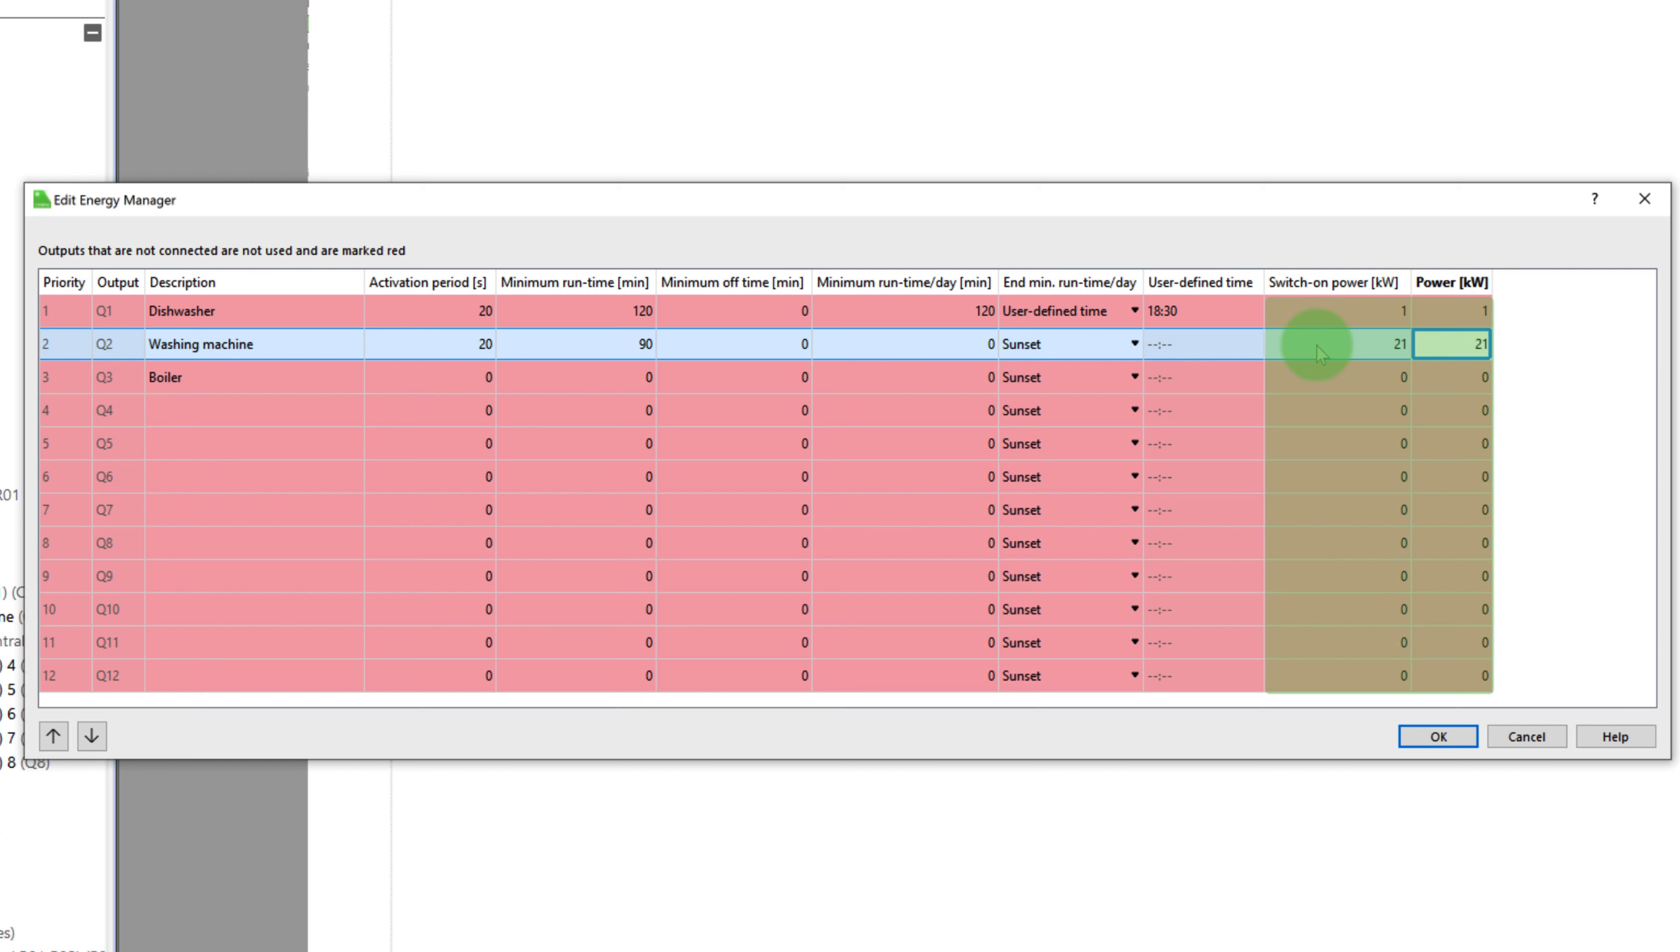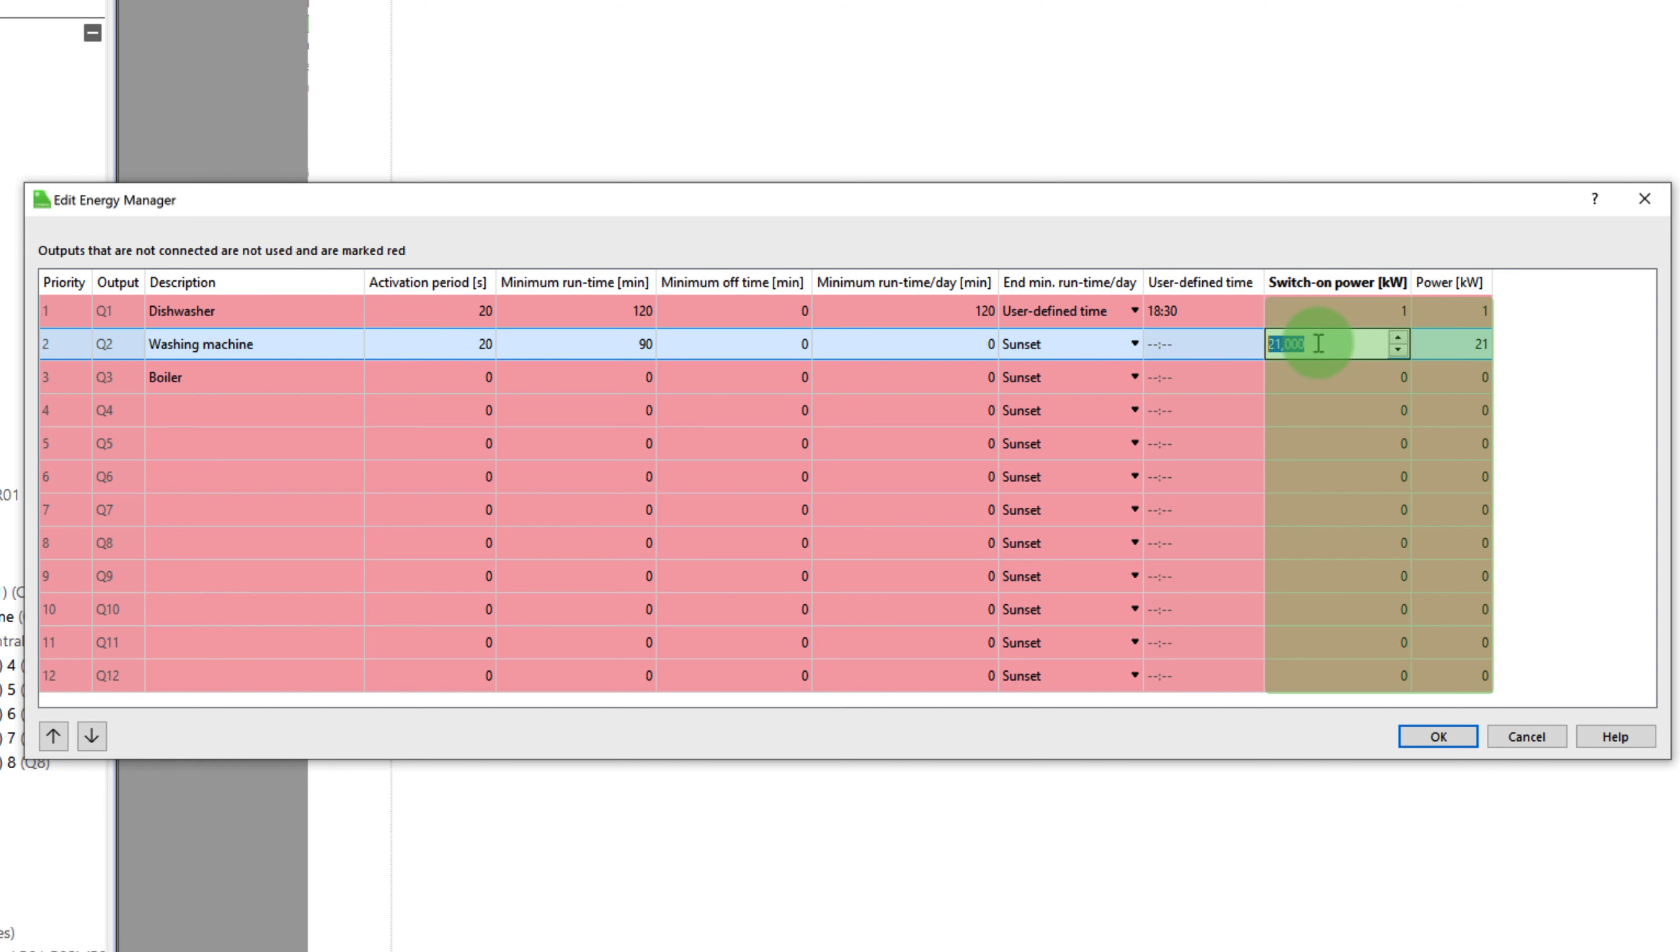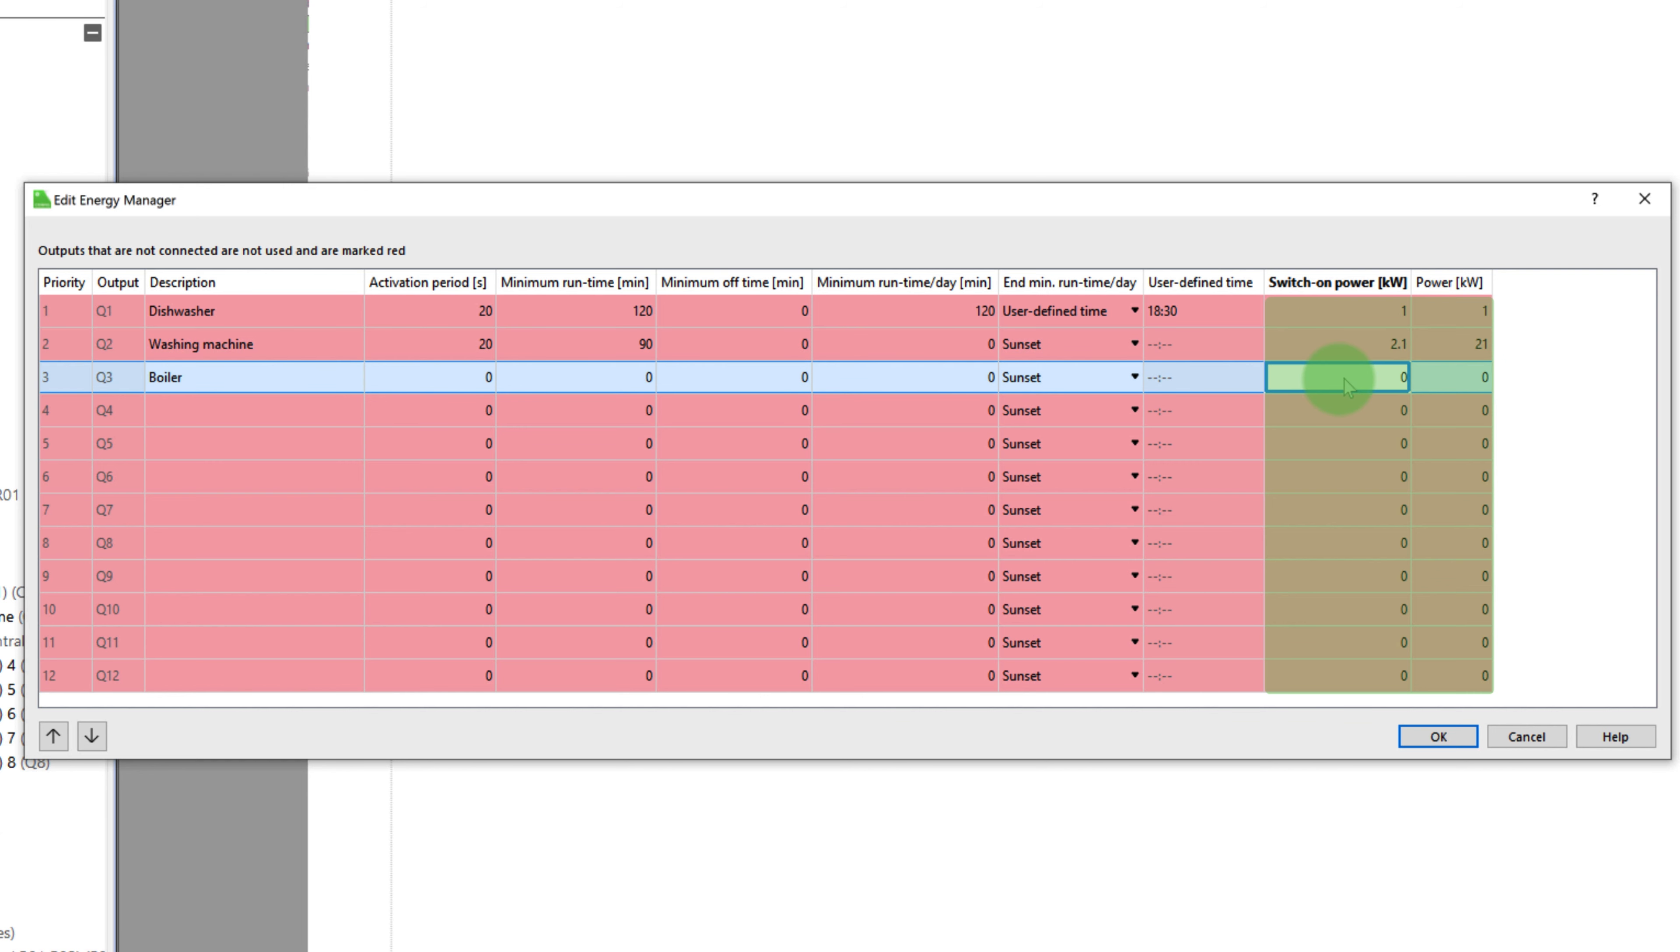For example, by sunset or by a user defined time. The switch on power specifies how much surplus power must be available for an output to switch on for a device. However, please be careful here, this variable does not correspond to the switch on current and the resulting switch on power of the electrical device.